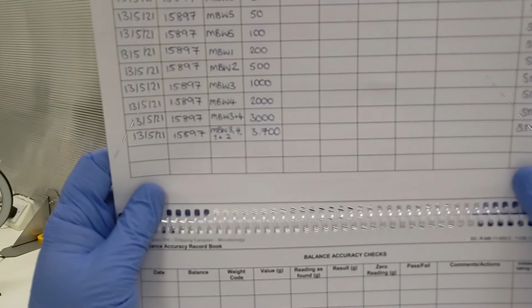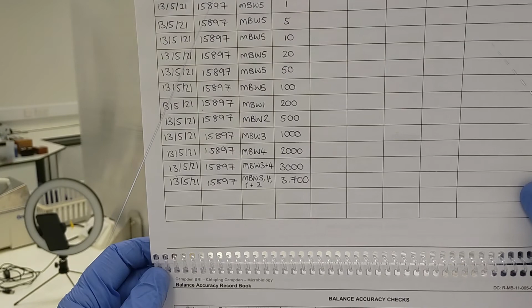We can also look at any records that the laboratory may do on a daily or weekly basis to verify the ongoing performance of the balance and that it's operating within parameters that they've requested. So presumably that would be done annually and these would be done monthly or weekly? Yes, or daily. Okay. And again, you've got document control up here, so it's all controlled, and that's in the appropriate laboratory book.